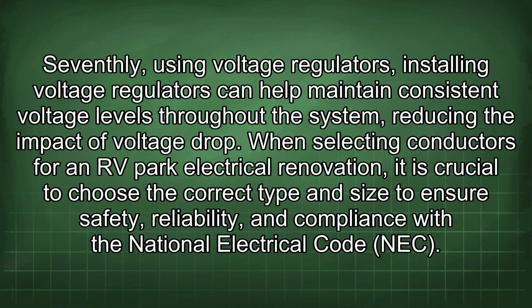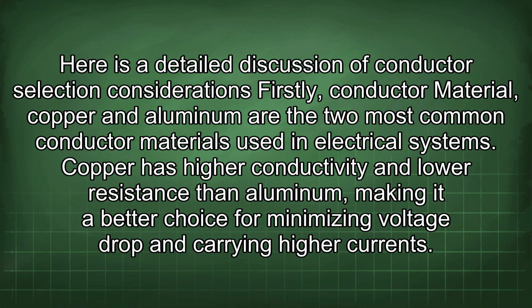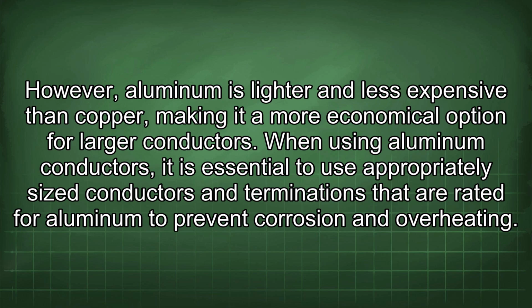When selecting conductors for an RV park electrical renovation, it is crucial to choose the correct type and size to ensure safety, reliability, and compliance with the National Electrical Code (NEC). Here is a detailed discussion of conductor selection considerations. Firstly, conductor material. Copper and aluminum are the two most common conductor materials used in electrical systems. Copper has higher conductivity and lower resistance than aluminum, making it a better choice for minimizing voltage drop and carrying higher currents. However, aluminum is lighter and less expensive than copper, making it a more economical option for larger conductors. When using aluminum conductors, it is essential to use appropriately sized conductors and terminations that are rated for aluminum to prevent corrosion and overheating.